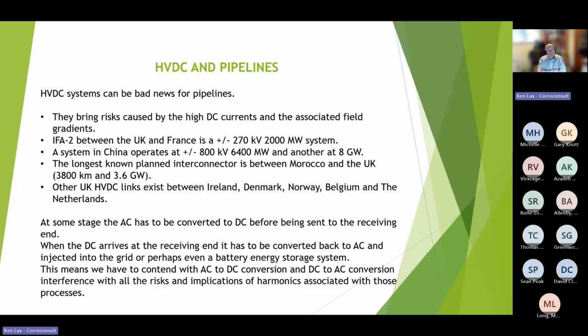Now, HVDC systems can be bad news for pipelines because, again, depending upon the configuration, you can have large amounts of current flying around close to the pipeline, which we don't want. And these HVDC systems are cropping up more and more as countries are working together to shovel around the power. If they've got an excess of power, they can shuffle it off to somewhere else. And then in turn, that can go to another country. When the things change, it can change direction. But at the end of the day, we really have to take account of these risks and we have to quantify them.